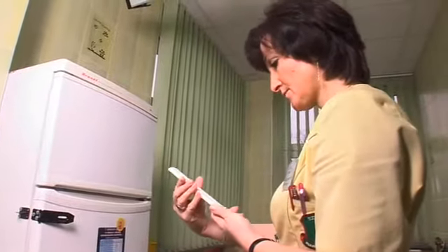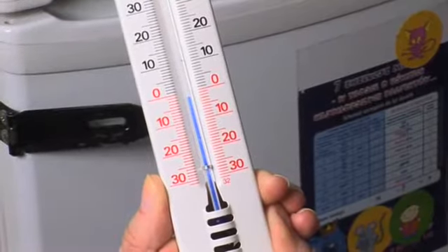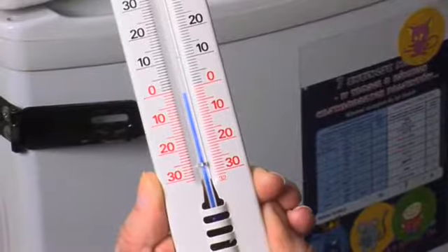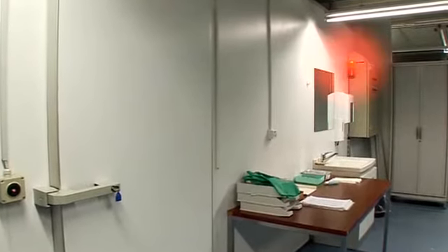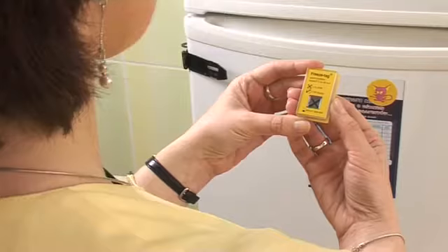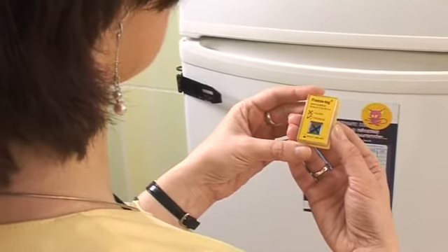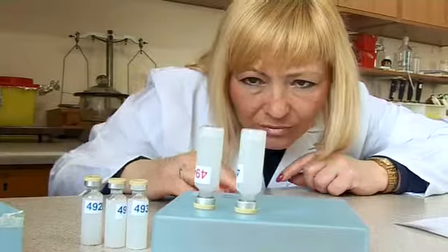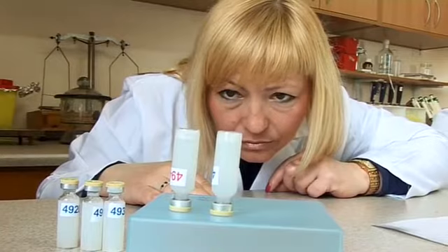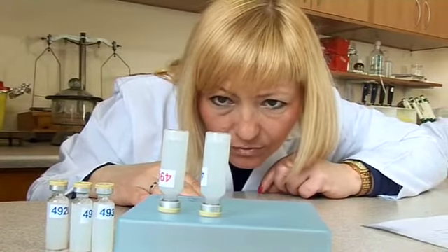Although a thermometer is not an ideal temperature monitoring device, it can show that the current temperature of the refrigerator is below zero. Likewise, the storage facility alarm system can warn responsible officers about freezing. Similarly, freeze indicators can also warn health workers about freezing temperatures. In all these situations, the shake test should be conducted.